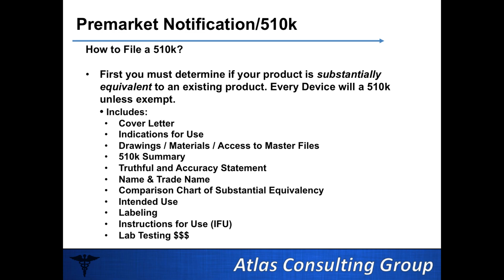And the instructions for use, which is basically the booklet of how to use your product. It could have sterilization instructions in there. And it's important because you have to recommend a way to sterilize the product that hospitals can actually do. If you tell them they have to use ETO sterilization and a hospital doesn't have ETO sterilization, they can't just use steam sterilization. Or if you tell them you want a 5-minute gravity cycle on a steam sterilization and they only do a 4-minute on everything, they're most likely not going to want to program their machine special for your device. So it's important to know what the hospitals can do before you instruct them on how to use your device and before you write that. Lab testing.